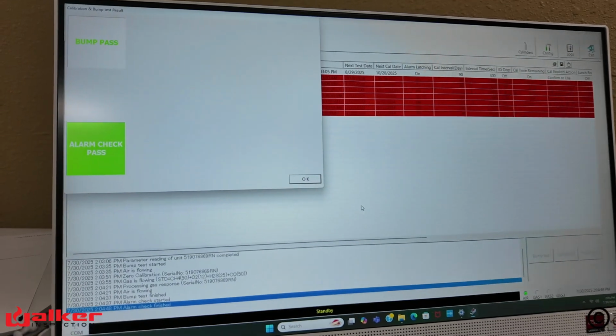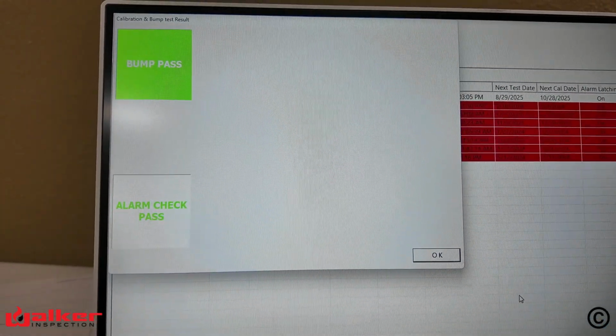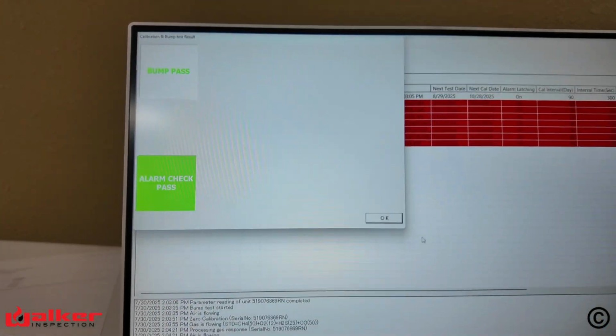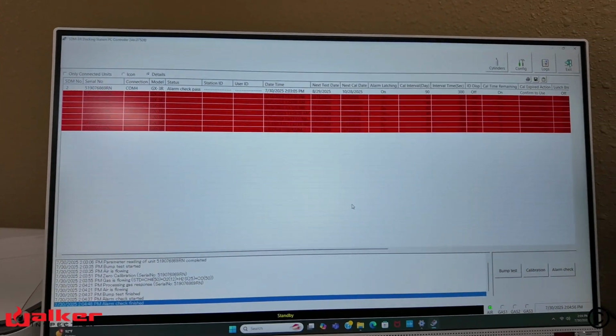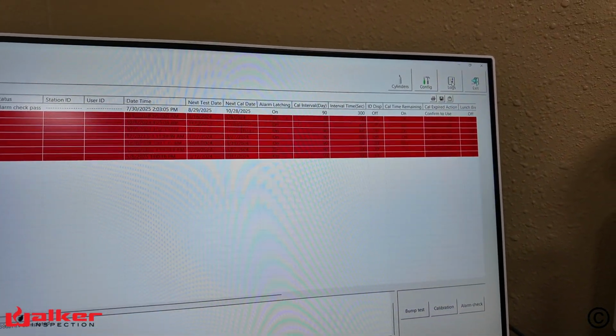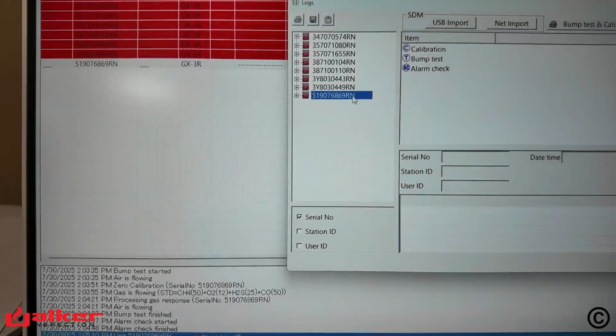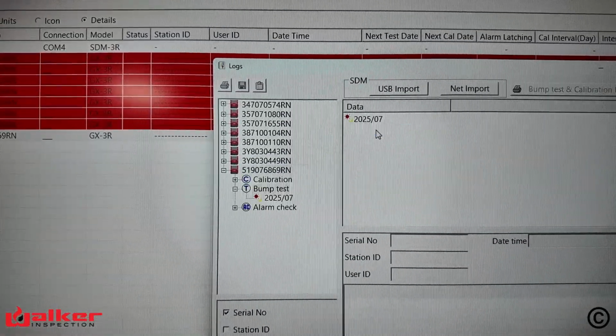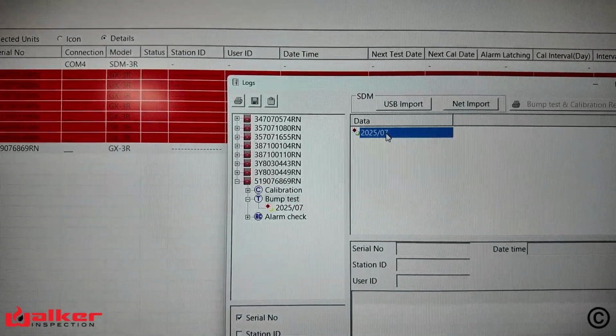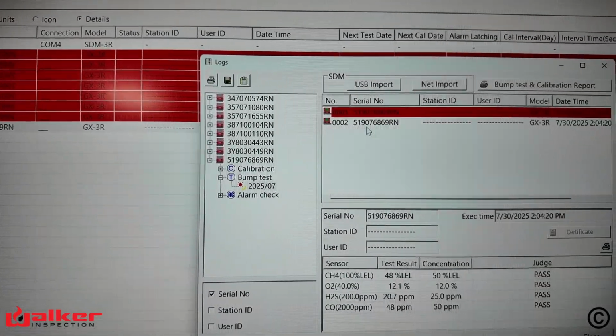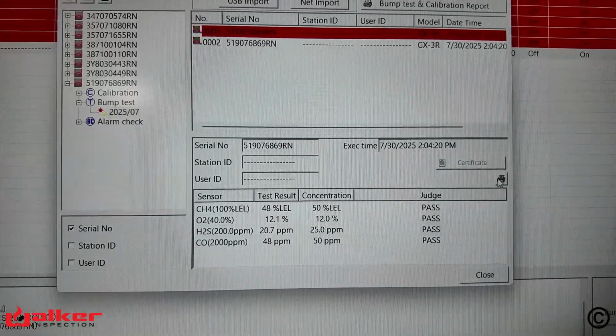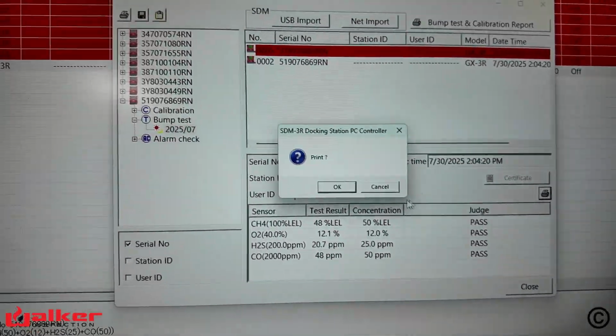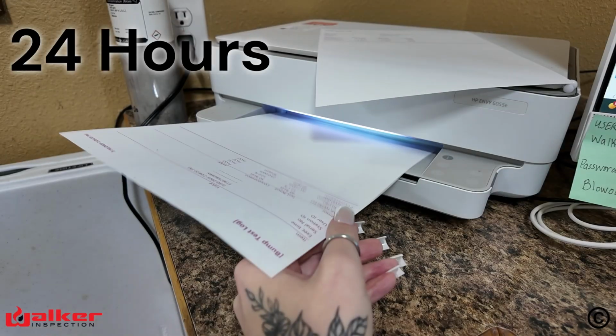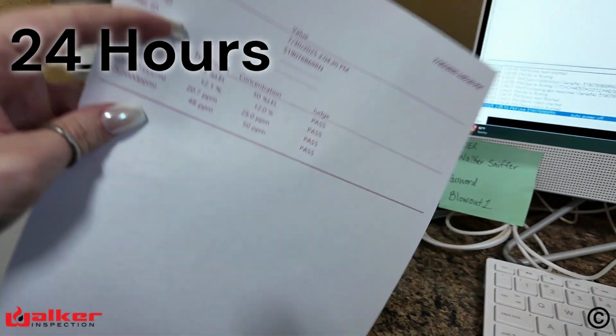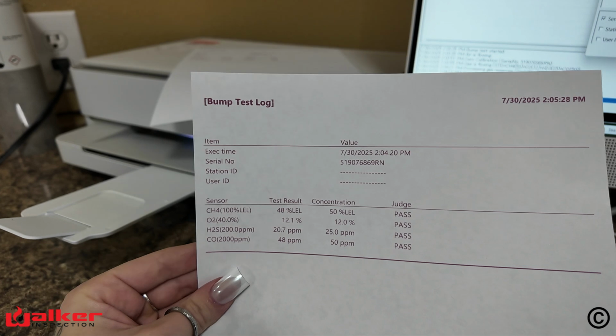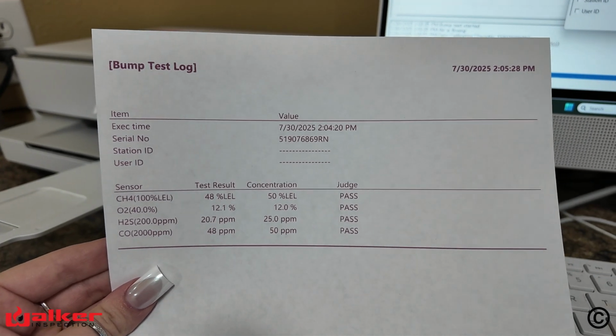And now this is an example of what one looks like when it is passed. It blinks green bump pass and print the bump certificate. The printing process is the same. Click top right-hand side on Logs. Double-click on the serial number for the monitor being tested. Double-click on the year and the month, and it will display the information for the test. You're going to click on the printer icon, and it will print off the bump certificate. A bump test needs to be done within 24 hours of the job for the confined space kits. This documentation needs to be in the kit as well as it will need to be turned in with the paperwork at the end of the job.